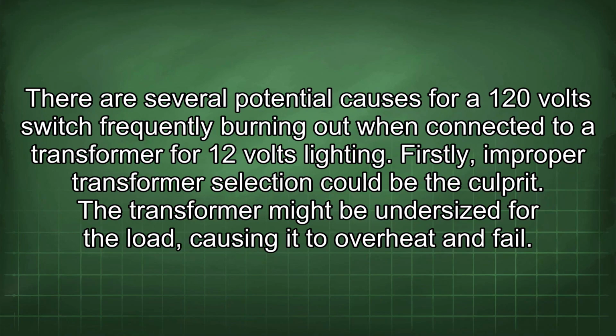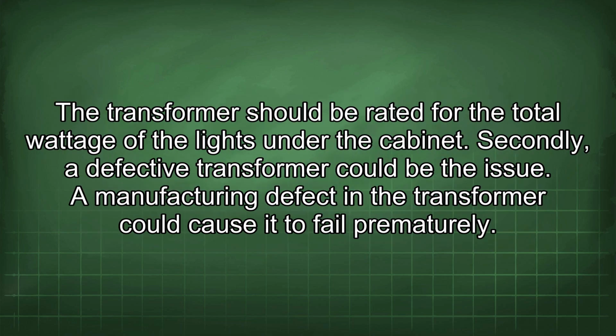There are several potential causes for a 120-volt switch frequently burning out when connected to a transformer for 12 volts lighting. Firstly, improper transformer selection could be the culprit. The transformer might be undersized for the load, causing it to overheat and fail. The transformer should be rated for the total wattage of the lights under the cabinet. Secondly, a defective transformer could be the issue. A manufacturing defect in the transformer could cause it to fail prematurely.